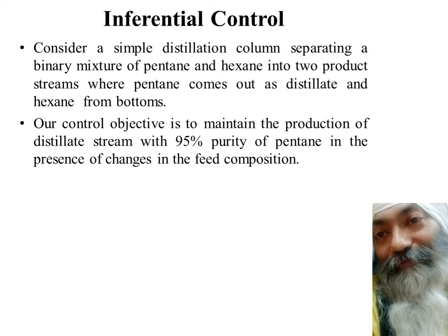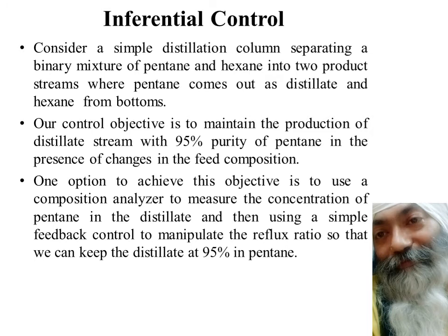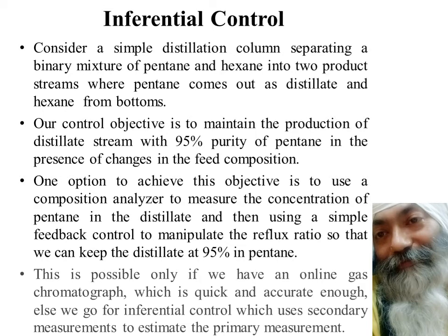We have the control objective of maintaining 95% purity of pentane in spite of changes in feed composition. To achieve this objective, we would normally use a composition analyzer to measure the concentration of pentane in the distillate and use simple feedback control to manipulate the reflux ratio to keep the distillate at the required set point of 95% pentane. However, the issue with this kind of simple feedback control is that normally we do not have online gas chromatographs which are quick as well as accurate enough.